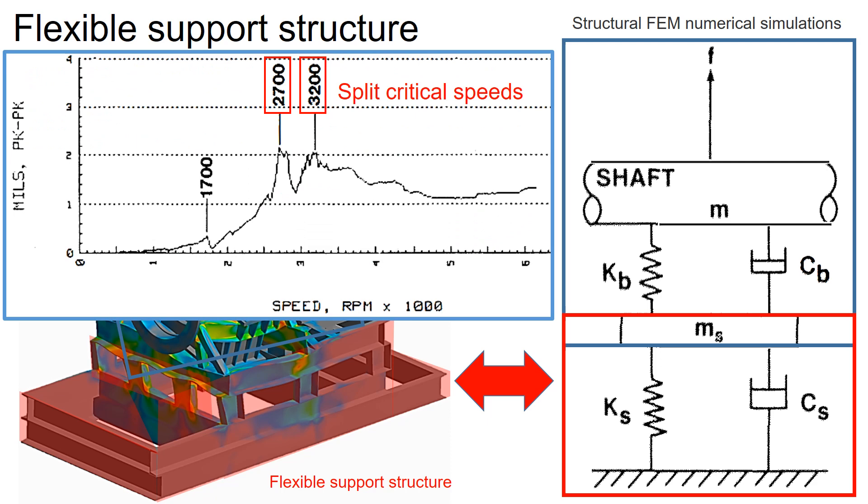In certain cases with flexible support, critical speeds can be split, as shown in this speed versus vibration amplitude plot from the measured data. Identifying flexible support characteristics is key to accurately capturing the critical speeds.